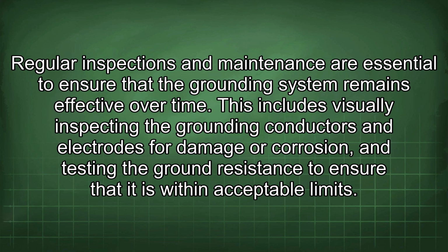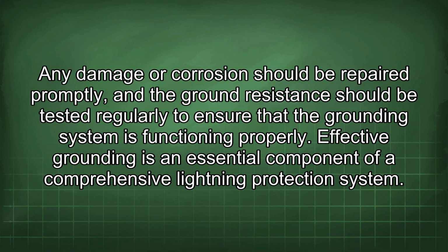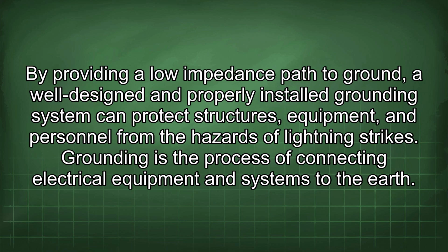Regular inspections and maintenance are essential to ensure that the grounding system remains effective over time. This includes visually inspecting the grounding conductors and electrodes for damage or corrosion, and testing the ground resistance to ensure that it is within acceptable limits. Any damage or corrosion should be repaired promptly, and the ground resistance should be tested regularly to ensure that the grounding system is functioning properly. Effective grounding is an essential component of a comprehensive lightning protection system. By providing a low impedance path to ground, a well-designed and properly installed grounding system can protect structures, equipment, and personnel from the hazards of lightning strikes.